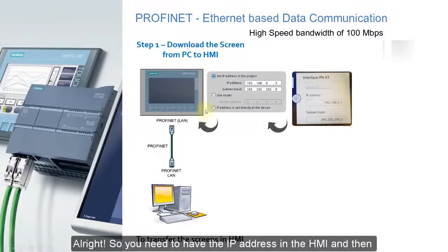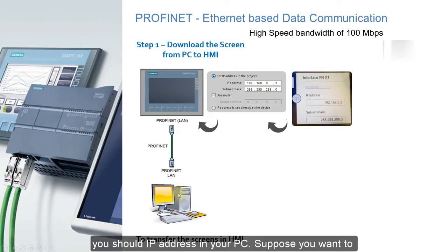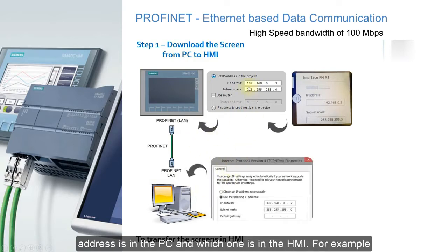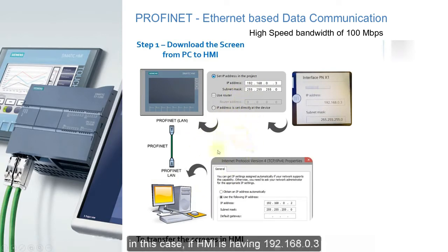You need to have the IP address in the HMI, and then you have to have an IP address in your PC. Suppose you want to download the screen from the PC to the HMI, we have to check which IP address is in the PC and which one is in the HMI. For example, if your HMI has 192.168.0.3, in the PC it should be 192.168.0.2.